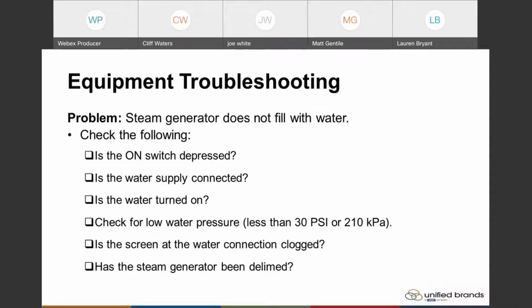Has the steam generator been delimed? Again, let's make certain we keep that delimer, and based upon the operation of your equipment is what actually drives the need to delime your HyperSteam unit. Why is that? Because the boiler again is enclosed, you can't see it, so you can't tell that it's dirty, right? So service light comes on, again, let's revert to at least trying to delime it. When a service light comes on initially, remember what I mentioned a couple slides ago, within 10 minutes that service light comes on, that's exactly when you need to go to your deliming.